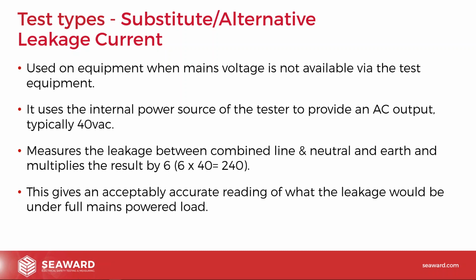It is a very good test, because it allows you to do a leakage test. Unfortunately, you can't turn on things like soft starts, relays, contactors, so it is only checking the input side of the device really. But it's giving you an AC measurement. I said to you before, there is a difference between AC and DC. And if we've got capacitive leakage, the AC test, or the substitute alternative leakage test, will pick up those leakages as well. So you get a better picture of how it's going to perform when you actually apply the AC mains to it. So this substitute alternative leakage test is a very useful test.